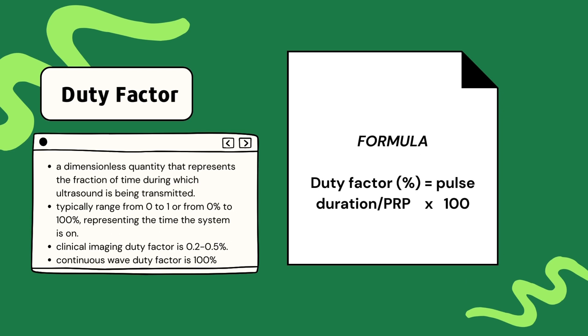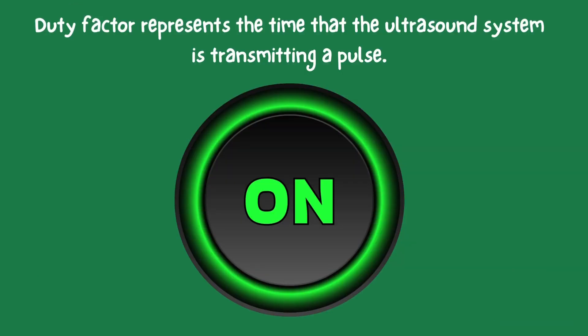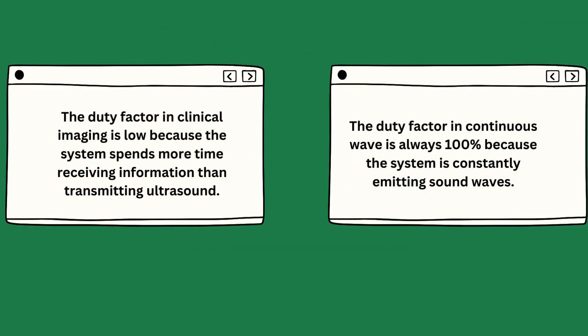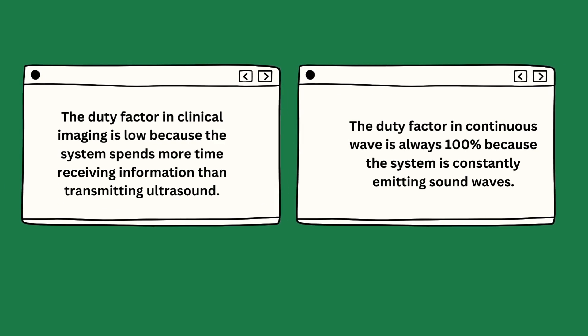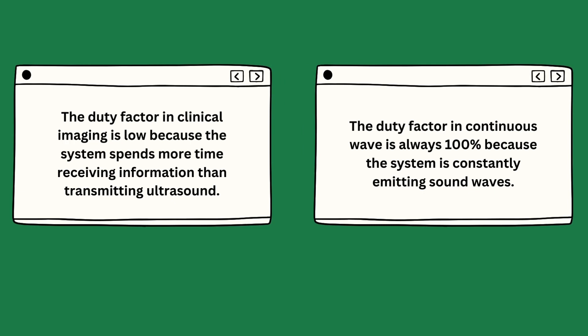Finally, let's discuss duty factor. Duty factor is represented as a dimensionless quantity, giving us insight into the fraction of time during which ultrasound pulses are actively transmitted by the system. Think of duty factor as a percentage indicating how much time the ultrasound system spends actively transmitting. In clinical imaging, duty factor typically ranges from 0.2% to 0.5%, representing a very small fraction of time during which ultrasound is emitted. This is because the ultrasound system spends way more time receiving than it does actually transmitting.